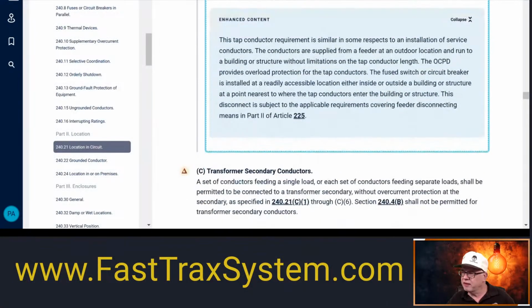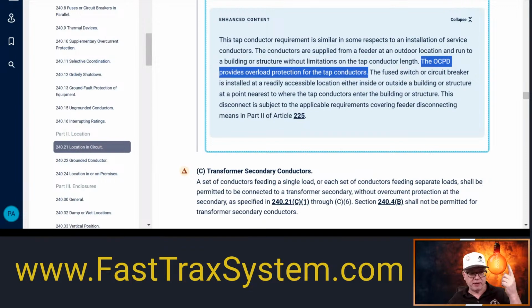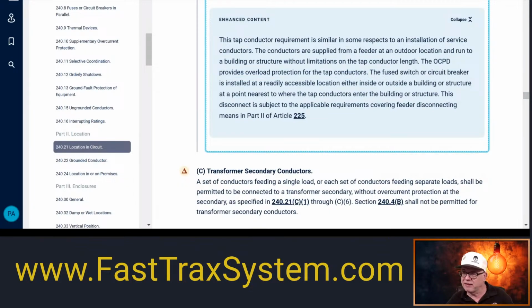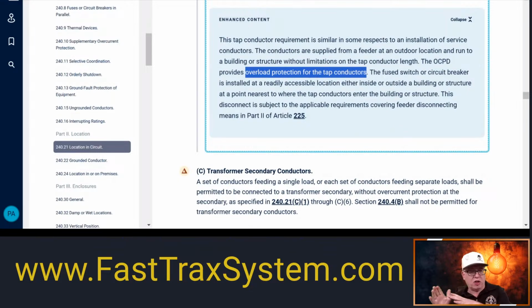And then it says the overcurrent protective device provides overload protection for the tap conductors. That's right, because it's coming from the feeder, and it's coming from the feeder tap outside, unlimited length, okay? And again, it has no protection at the tap. Wherever it's tapping, there's no protection there. So the overcurrent device provides overload protection for the tap. That's why we're required to limit the amount of current that can be on those conductors. You saw earlier, we're limiting the amount of current, so we're going to provide some overload protection there.